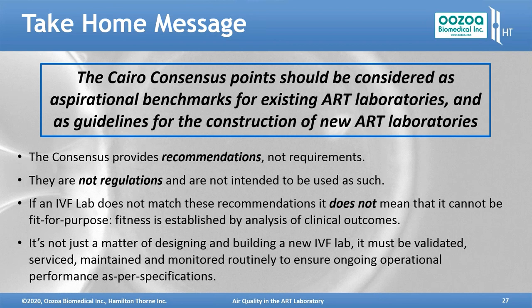But if something were to go wrong 2 weeks after one of those validations, you wouldn't find out for another 50 weeks. And you'd be wondering why things were drifting, or why you got more variability in your outcomes. That's why it's important to have these testing instruments available in-house. So for particulates and for VOCs, we recommend that every lab should have at least one of each of those, so you can do this monitoring independently, regularly. With a new lab, you might do it more frequently than once you've got the system bedded down, but we still would monitor at least weekly.